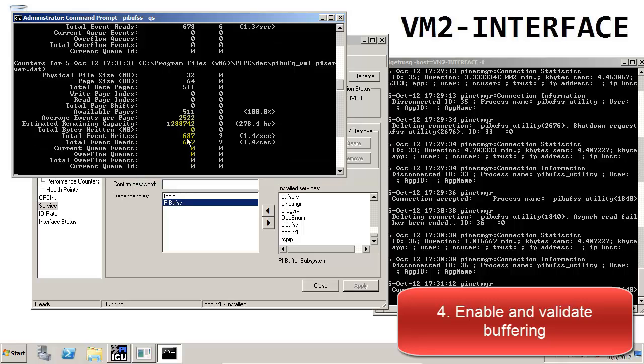Right now we can see that the total event writes and the total event reads match, and if we look at the current queue events, it's zero. This means that data is being written to the buffer and being read from the buffer, but there are no queued events, which means the data is passing straight through the buffer to the PI Server.